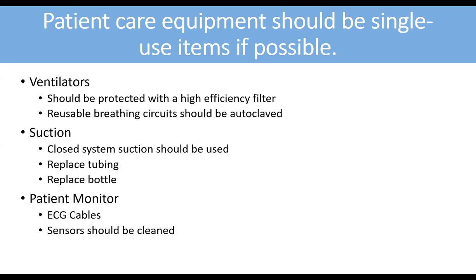For patient care equipment that should be single use: protection filters should be single use, and some reusable circuits need to be autoclaved. Some breathing circuits are single use only and must be thrown away, and the water trap needs to be replaced. Suction system tubing should be replaced, and bottles replaced if single use. Some bottles that are multiple use need to be autoclaved to make sure there's no cross infection. ECG cables need to be cleaned, and sensors like SpO2 also need to be cleaned.